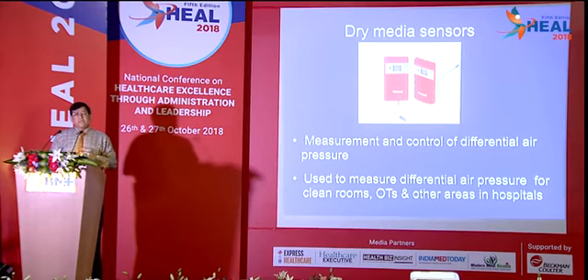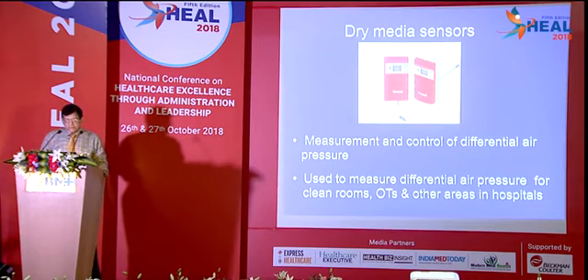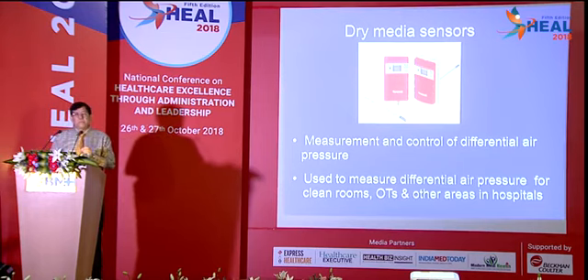We have dry media sensors, a part of the building management system, for measurement and control of differential air pressure. You will appreciate that there are many facilities where we have a zoning system. Like operation theatre, we have zoning; ICU, we have zoning; in any of the wards, we have zoning: patient areas, ancillary areas, auxiliary areas, sanitary areas. That is how we create the zones. PASA is the formula for students to remember. Now, these dry media sensors help in maintaining the differential pressure.